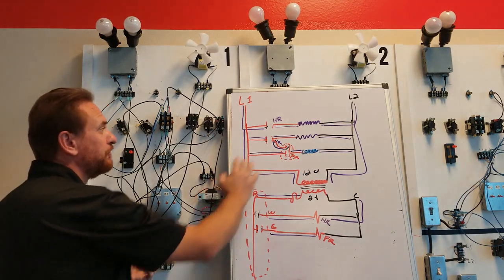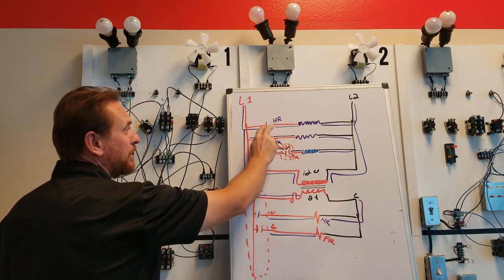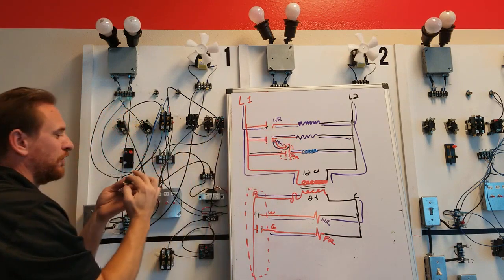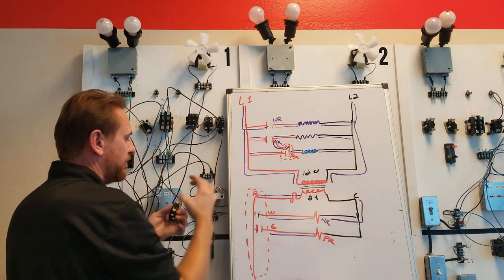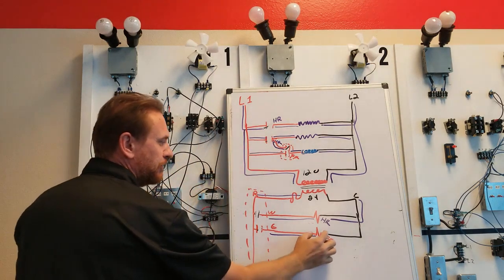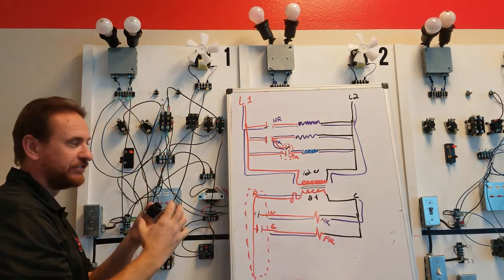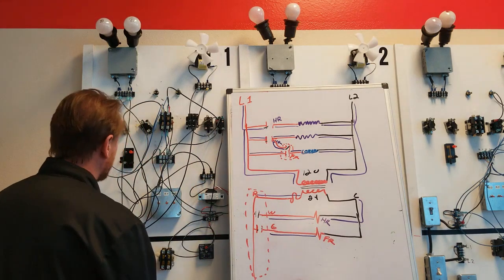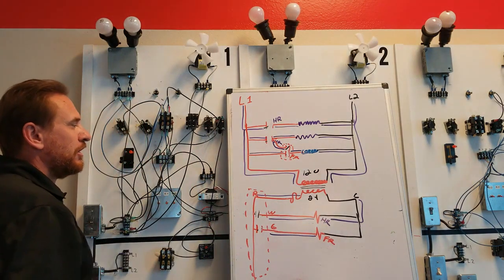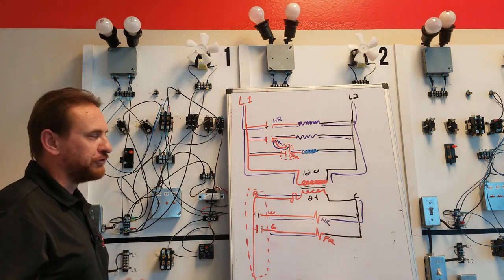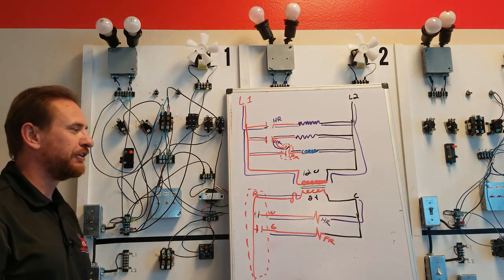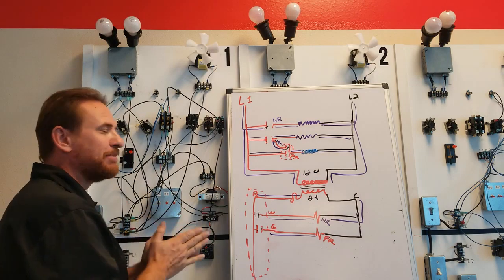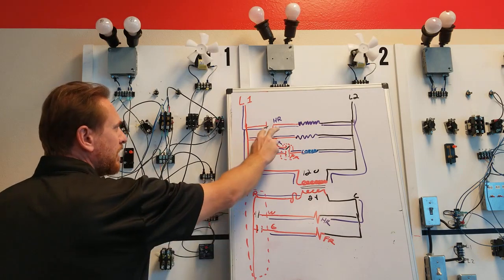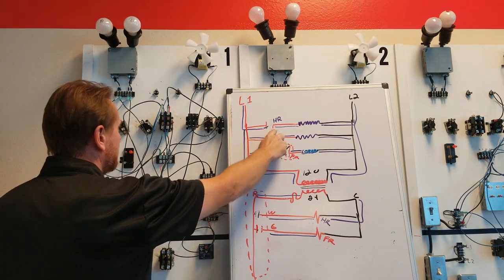What we're going to do is move, the wiring is going to stay the same. We're going to move these two wires over to this. We're going to move these two wires over to this. We're going to move these two wires down here to this. Same number of wires, but I'm going to use the one that's already mounted. You can do high voltage first or low voltage first. I always like to do high voltage first, low voltage last, but as long as you keep them separate, you're going to be okay. So here I have one wire coming in, one wire coming out.